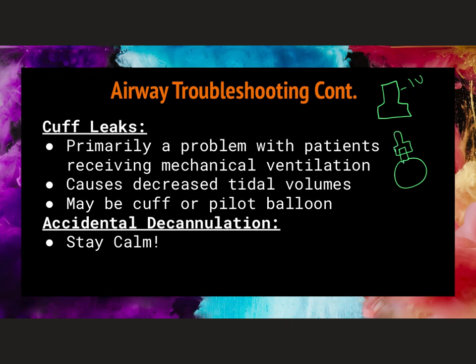and it's that one-way valve here that just got blown and it's slowly leaking out, and that red cap, and then you check on it your next rounds, and you see that the cuff pressure hasn't changed, you know it's a pilot balloon problem. And if the red cap fixes it, pass it on and report.